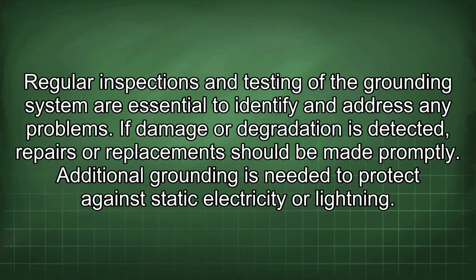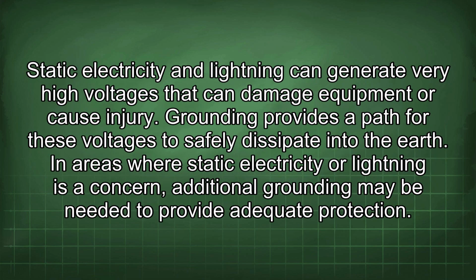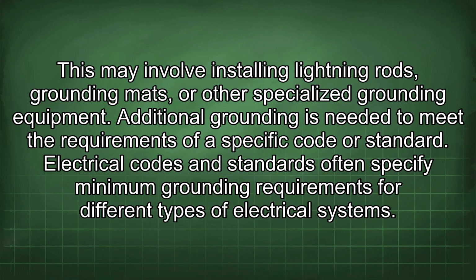Regular inspections and testing of the grounding system are essential to identify and address any problems. If damage or degradation is detected, repairs or replacement should be made promptly. Additional grounding is needed to protect against static electricity or lightning. Static electricity and lightning can generate very high voltages that can damage equipment or cause injury. Grounding provides a path for these voltages to safely dissipate into the earth. In areas where static electricity or lightning is a concern, additional grounding may be needed to provide adequate protection. This may involve installing lightning rods, grounding mats, or other specialized grounding equipment.